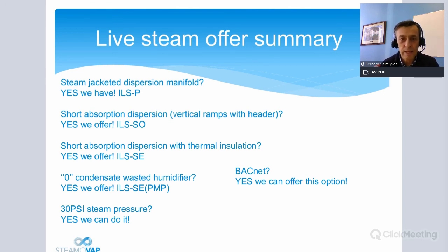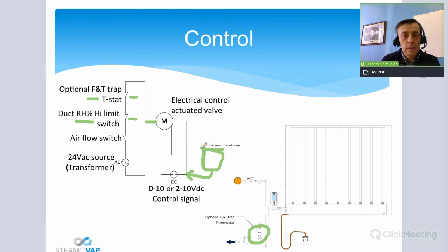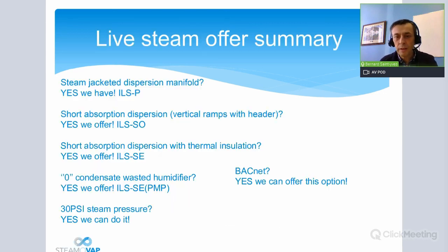And do we have BACnet? Yes, we do. If you have an engineer that wants to have a BACnet on the live steam humidifier, we will have, let me retrieve the control. So this device will be BACnet here. The room humidistat will be BACnet, and then we will take the 0 to 10 or 2 to 10 volt to the valve. Okay, so you will have a way to give the information to the live steam humidifier through BACnet, and then the rest is more traditional. So I think it's covered.